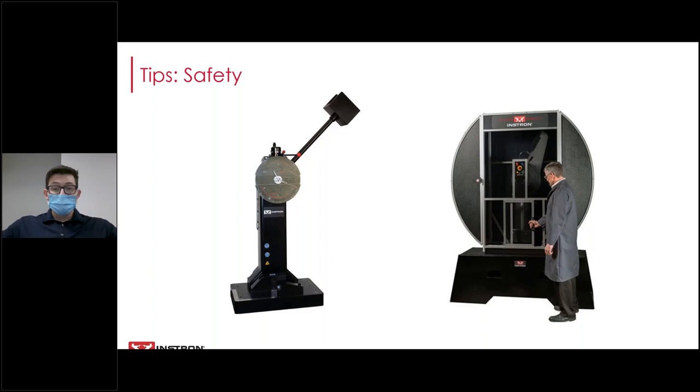And also, maybe some of you are familiar with this if you've used one of these manual frames, in order to latch the hammer back into this upward position, a lot of operators will physically catch the hammer when it's swinging back. And you have your hands in the vicinity of moving parts. Also, when that hammer comes down to catch it, over time that can certainly cause some force on your shoulder or arm. It's just something to keep in mind if you're considering an impact frame. It's safety and ergonomics.